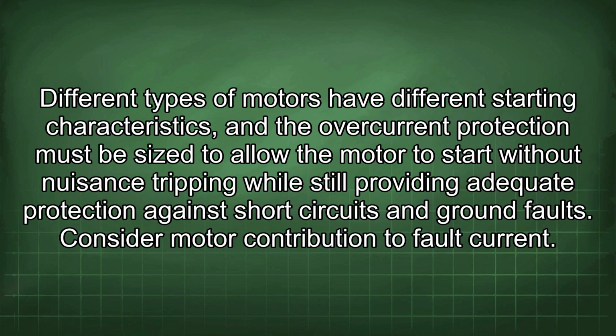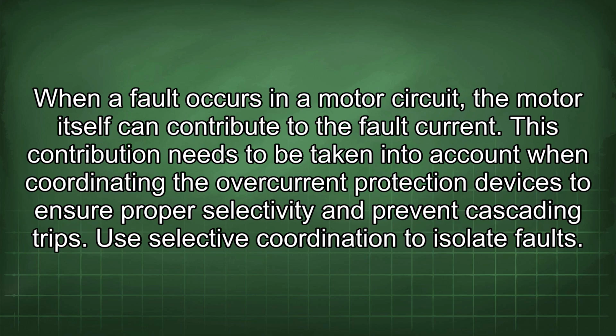Consider motor contribution to fault current. When a fault occurs in a motor circuit, the motor itself can contribute to the fault current. This contribution needs to be taken into account when coordinating the overcurrent protection devices to ensure proper selectivity and prevent cascading trips. Use selective coordination to isolate faults.